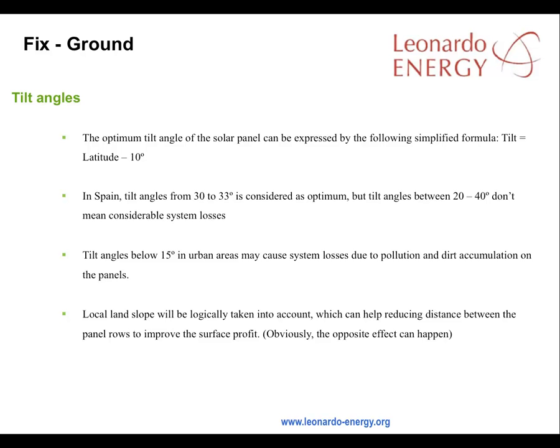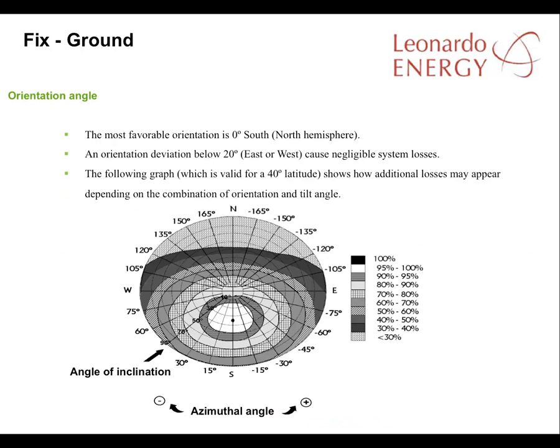Where the panel is installed on a southern facing slope, the slope can be used to reduce the distance needed between panel rows. In the northern hemisphere, the most favorable orientation is 0 degrees south. However, an orientation deviation of less than 20 degrees east or west will cause negligible system losses.